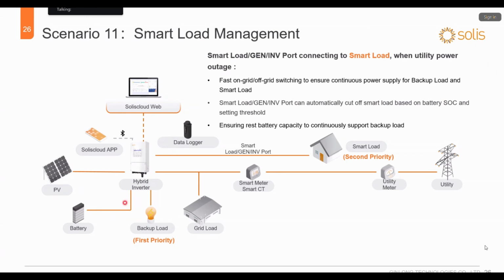So once this heavy load is turned off, the battery will be more available for the first priority load. In areas where they have more grid outages than normal, like 3 hours, 4 hours, if this secondary load is also running too much, it can drain the battery in a fast way. So once the grid is returned back, now you have two options. Either you can wait for the battery to be charged and then turn on this load, or you can set the limit, like whenever the grid is turned on, at the same time you can turn on this load.